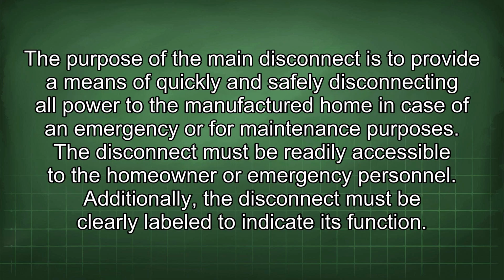The purpose of the main disconnect is to provide a means of quickly and safely disconnecting all power to the manufactured home in case of an emergency or for maintenance purposes. The disconnect must be readily accessible to the homeowner or emergency personnel. Additionally, the disconnect must be clearly labeled to indicate its function.